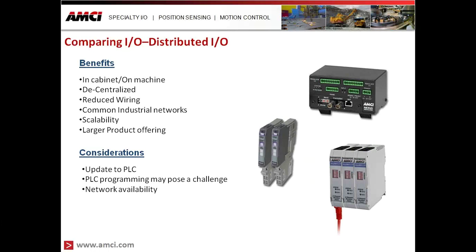When using distributed IO for your PLC system, some of the benefits are that you can mount it in the cabinet or directly on the machine — even in hazardous environments. It decentralizes the system, allowing you to locate IO closer to where the sensor is mounted, which reduces wiring. Distributed IO is available with many common industrial networks, and in some cases it's much more scalable since you're not limited to a rack construction. You also get a much larger product offering beyond what a single PLC supplier offers.